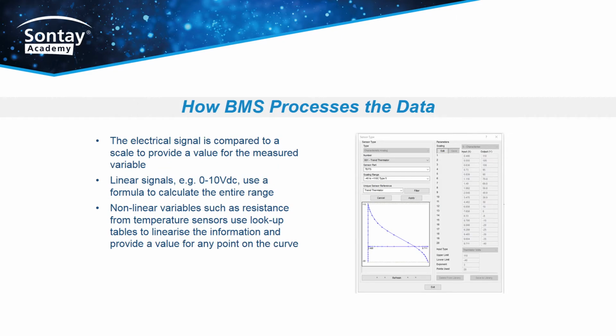How BMS processes the data. The electrical signal is compared to a scale to provide a value for the measured variable. Linear signals, for example 0 to 10 volts DC, use a formula to calculate the entire range. An example of this would be 0 would be 0 degrees and 10 volts could be 100 degrees. That's how the controller would read the scale.